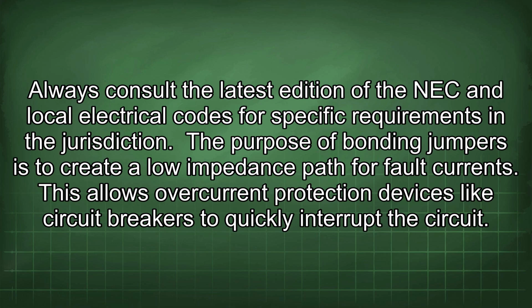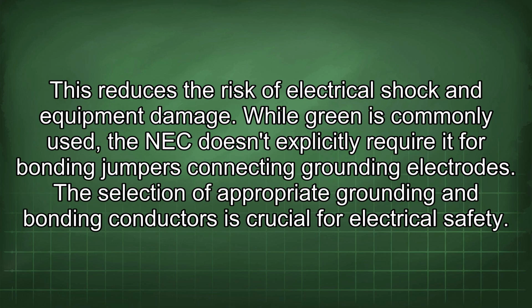The purpose of bonding jumpers is to create a low impedance path for fault currents. This allows overcurrent protection devices like circuit breakers to quickly interrupt the circuit. This reduces the risk of electrical shock and equipment damage. While green is commonly used, the NEC doesn't explicitly require it for bonding jumpers connecting grounding electrodes.